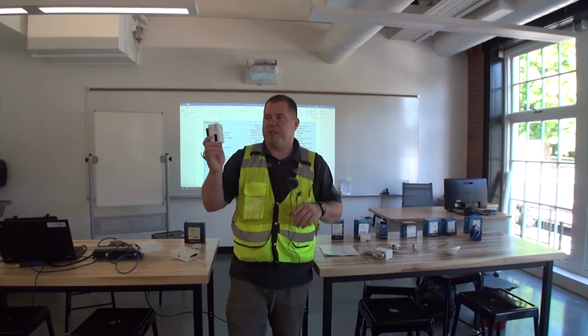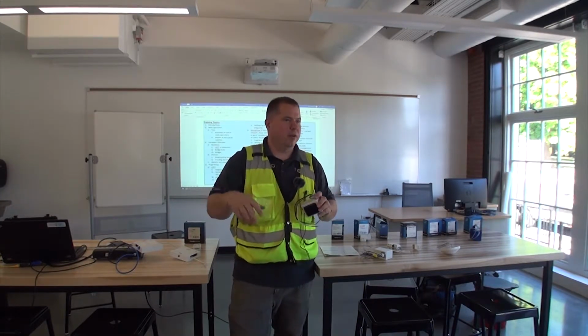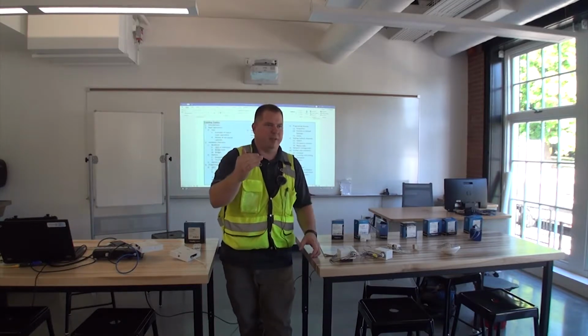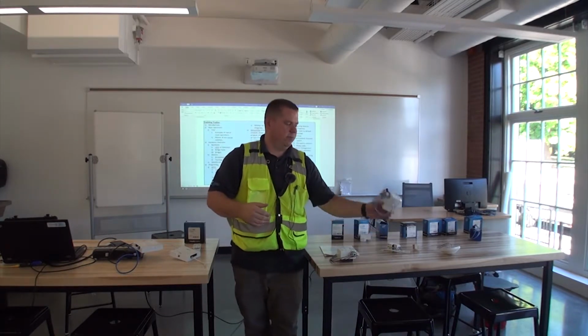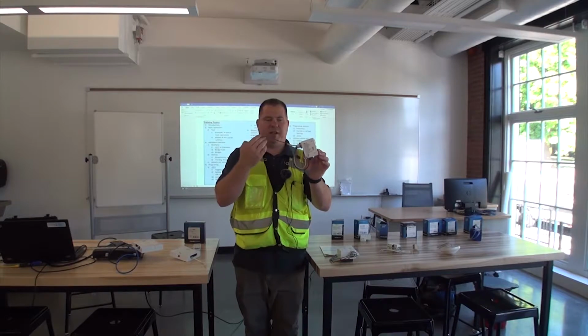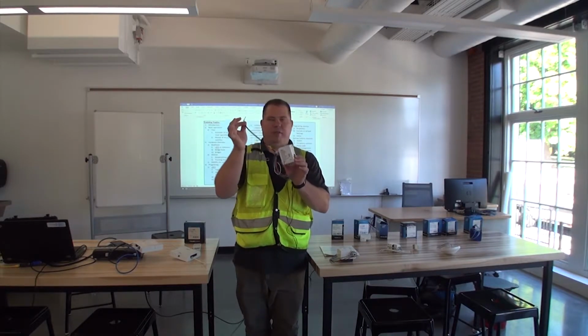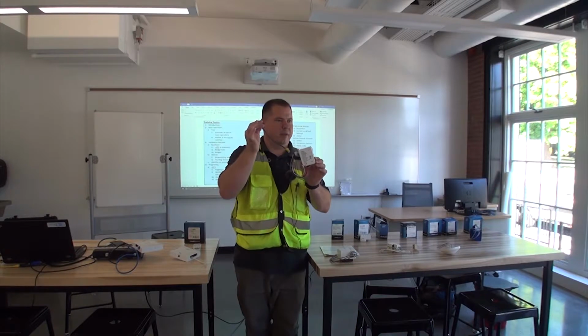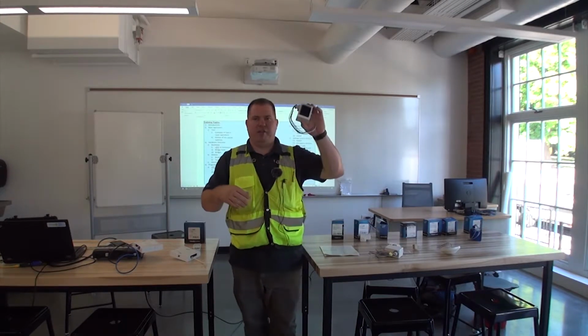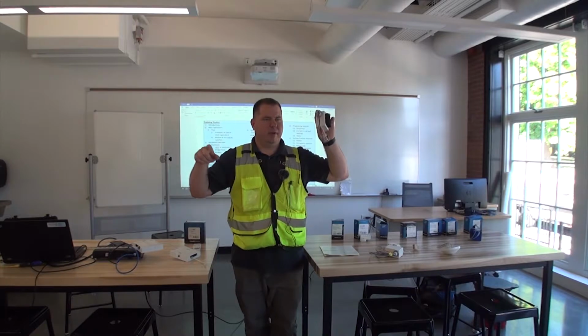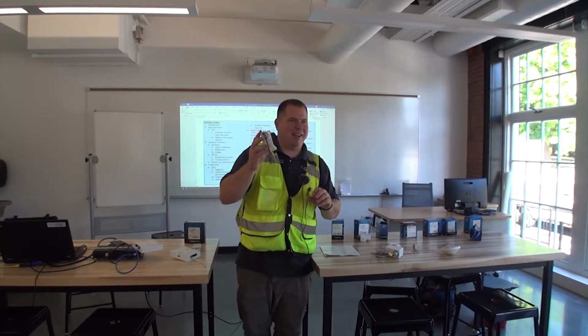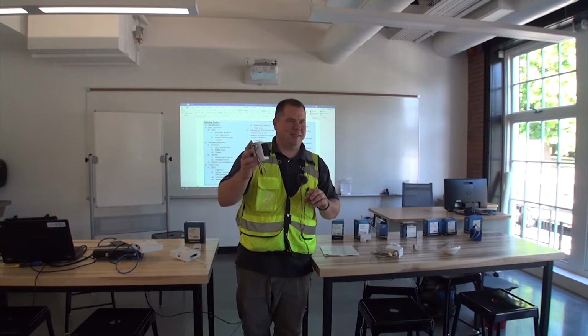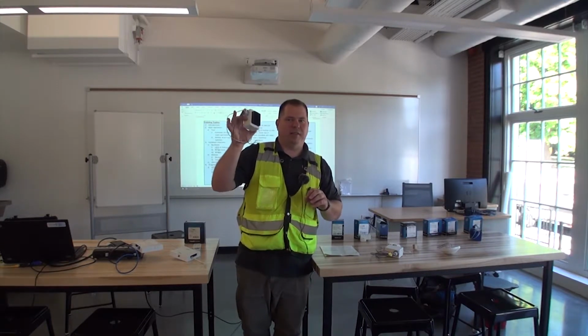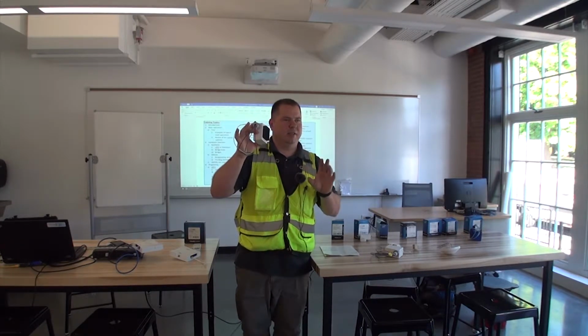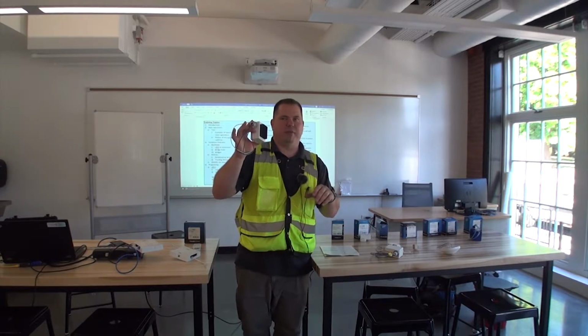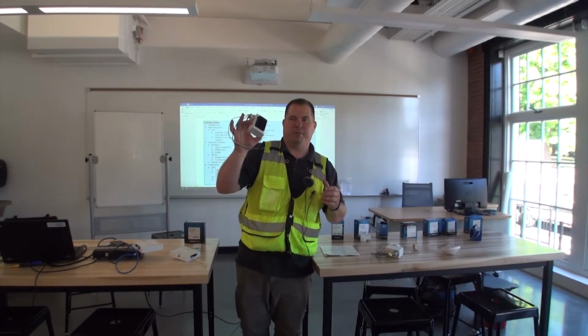It's phase dim, like a rheostat in your wall, like the old kitchen rheostat. You're literally taking 120 volts and bringing it down to 60 volts. Whereas with 0 to 10, it's 120 all the time, but you're syncing control via a low voltage 0 to 10 signal. This is literally changing the power in the sine wave. Because it's changing the sine wave, it cannot produce power on the bus. That's why this one doesn't produce power, because it's literally changing the sine wave. It doesn't stay 120 volts all the time, and that's why it doesn't produce bus power.